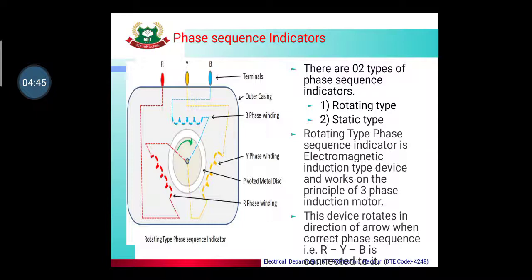In the rotating type phase sequence indicator, as seen in the diagram, there is a stator with a rotor in the center. A metal disc is mounted on a shaft, and three windings — R, Y, and B phase windings — are connected. This rotor rotates based on the working principle of a three-phase induction motor. The device rotates in the direction of the arrow when the correct phase sequence R-Y-B is connected to it.